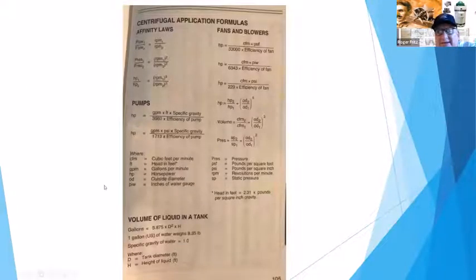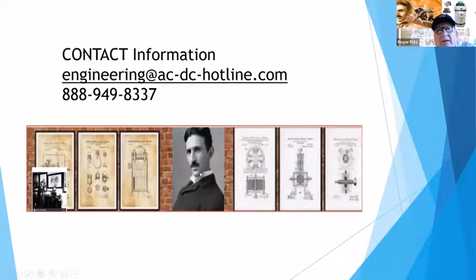So again, inside this little ISSA book, there's a lot of little formulas for fans and blowers, centrifugal applications, flow, amount of pressure, the amount of horsepower, so that you can really get it back to simple again and figure out the GPM of pumps, where the efficiency of that pump is, and the higher we keep that efficiency of the pump on the pump curve, the better off we are.